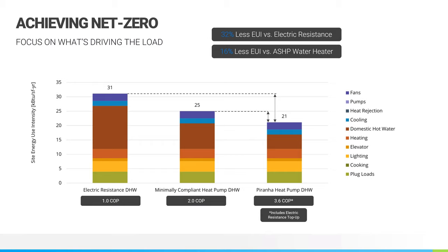So it's really imperative to run energy models, as well as really looking at what's driving that load for that particular building, which in the case of multifamily, it's going to be your domestic hot water, because it's based on the occupancy and not based on the outdoor weather.